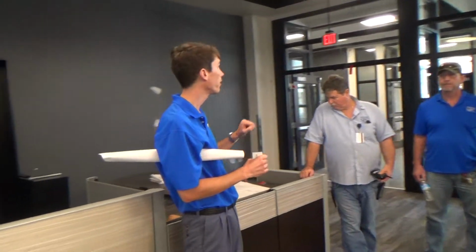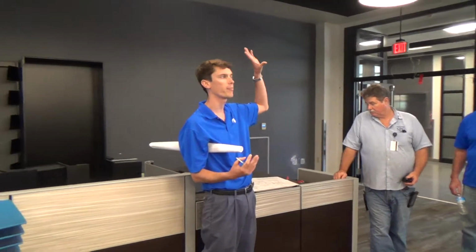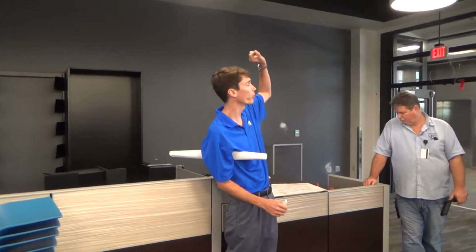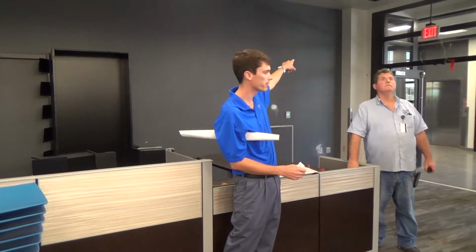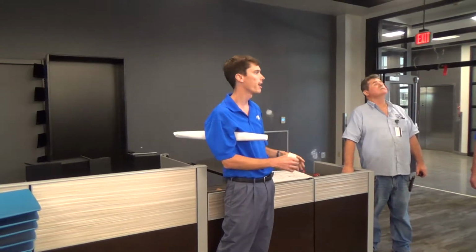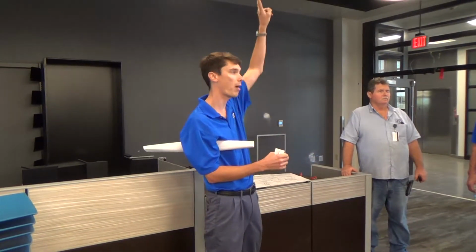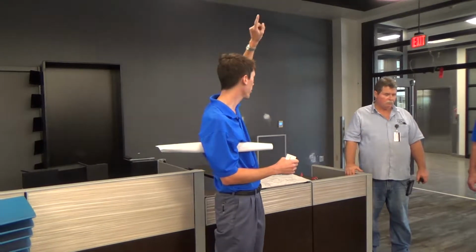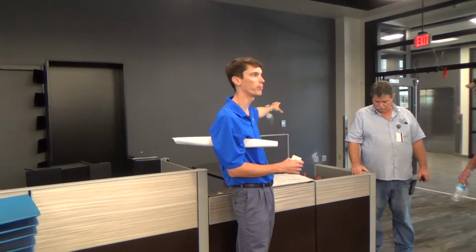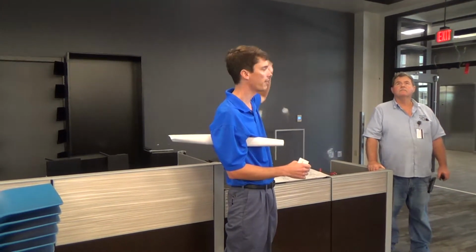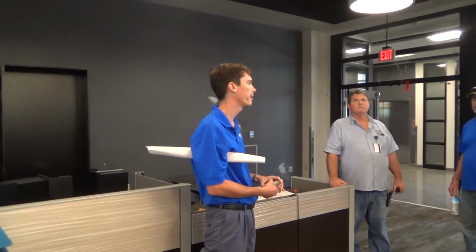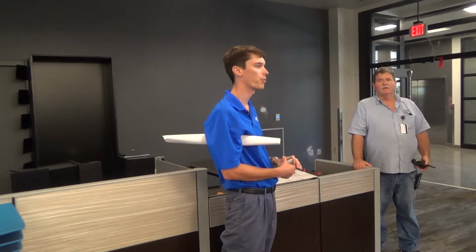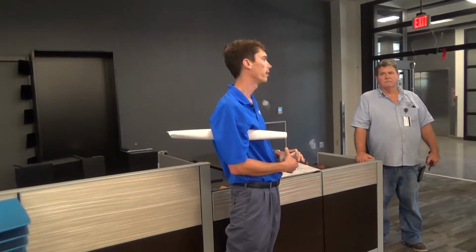So each switch leg that would, in a relay panel, have its own relay, has its own relay, but it's in the space now. So if, when you came in through this entrance here, that big room on the left has 2 switch legs. So we have 2 power packs in that room, and they're connected to the switches in the room and the aux sensors in the room, and then they're tied to a hub that goes back to this brain that we're going to look at.